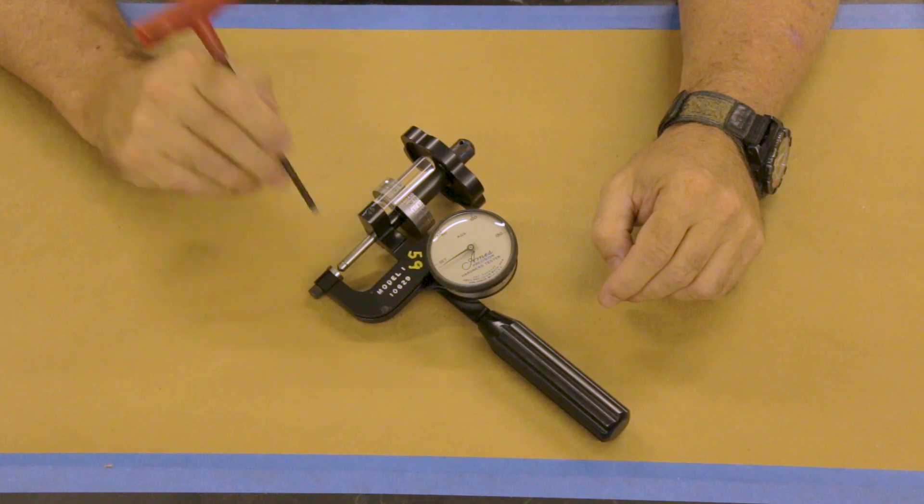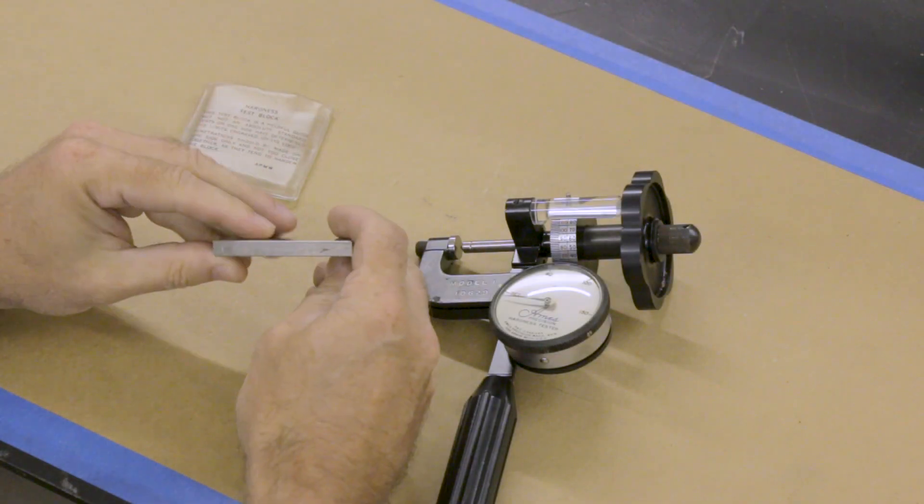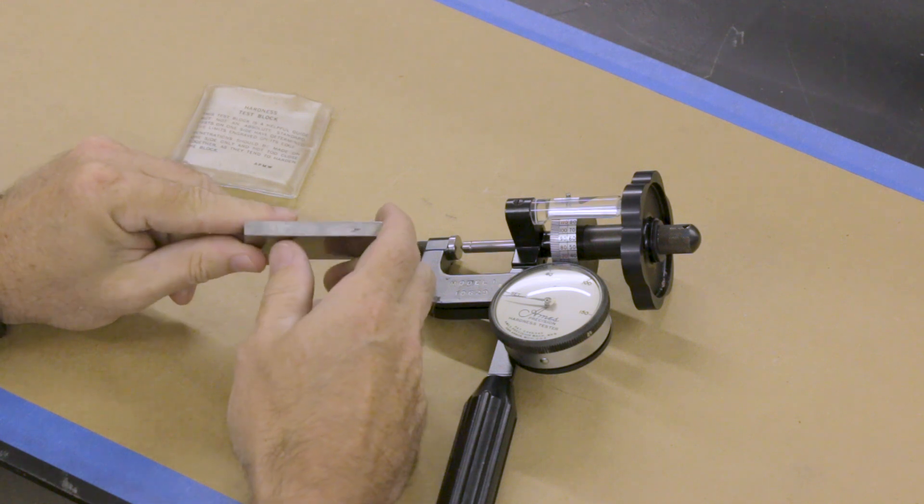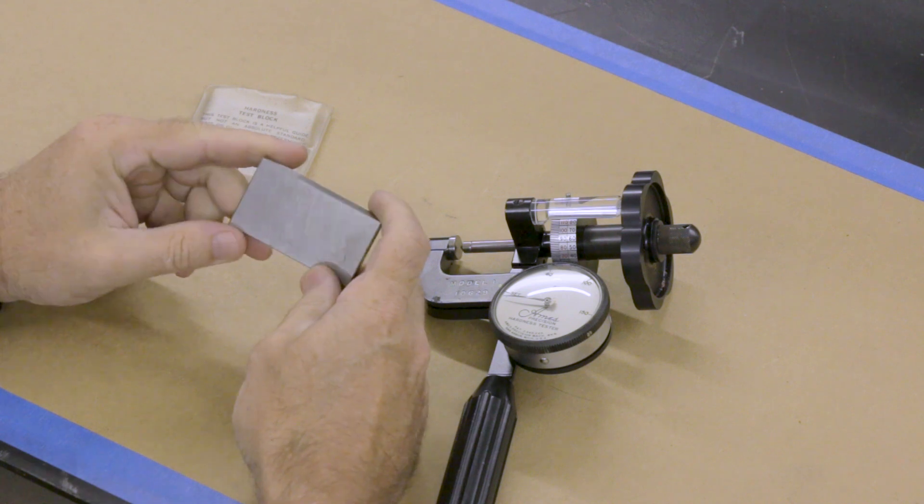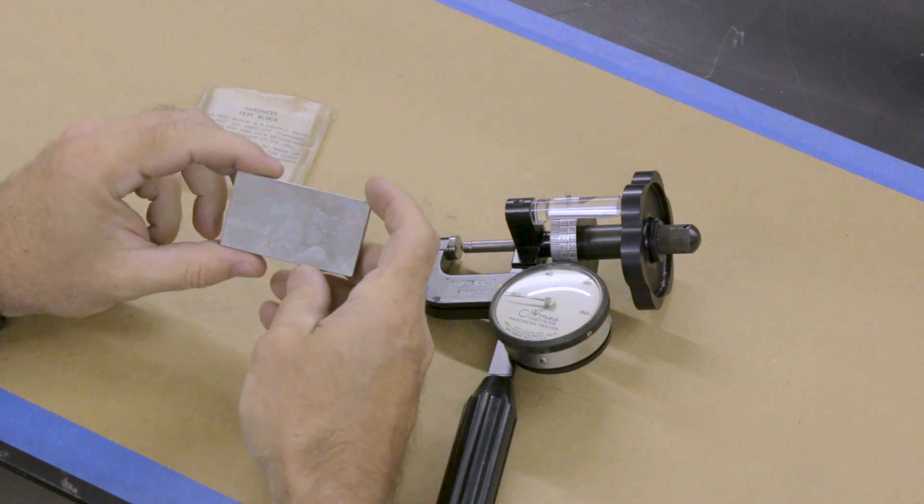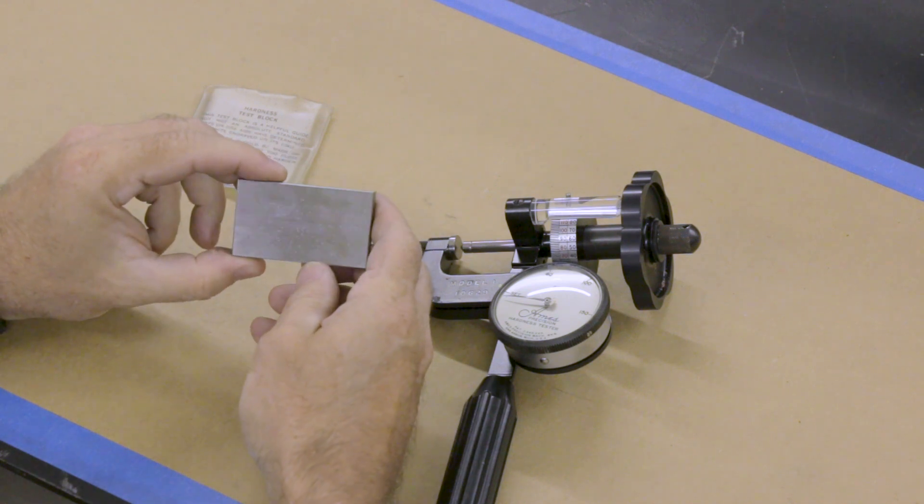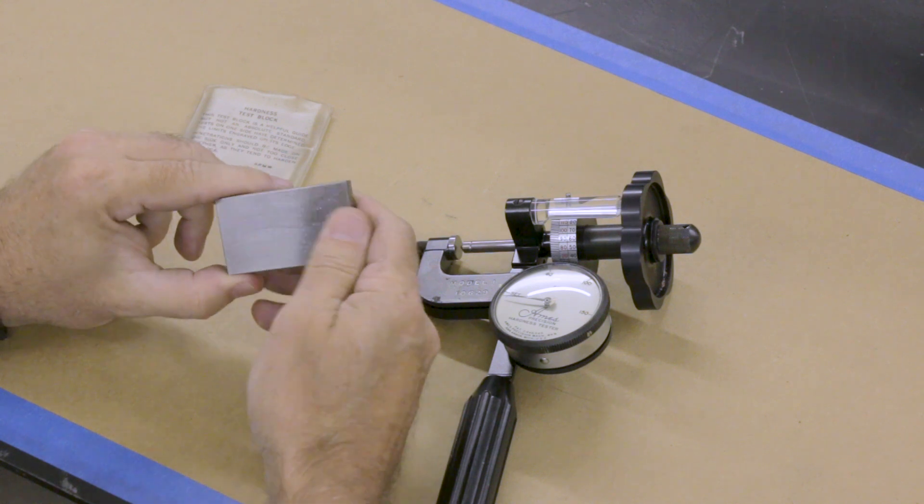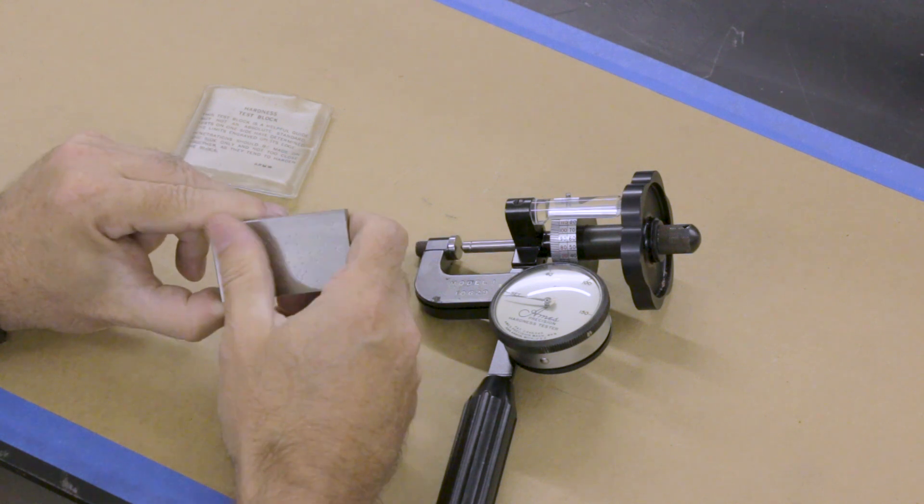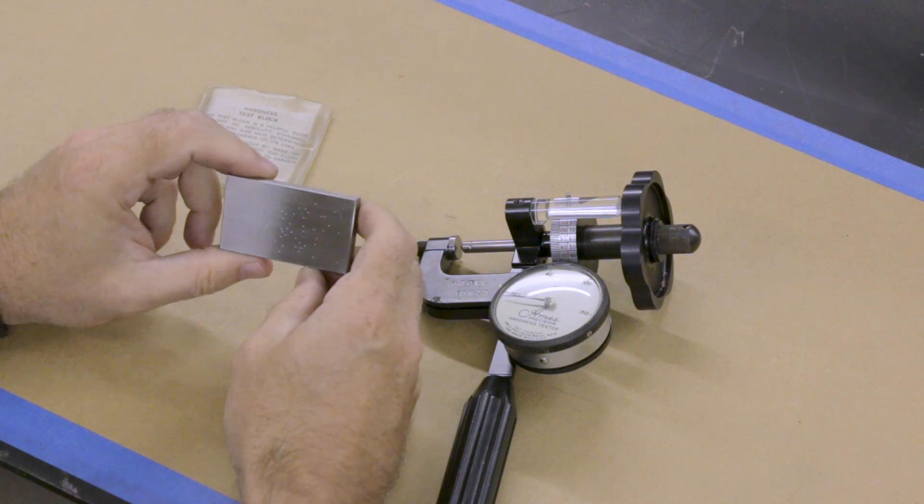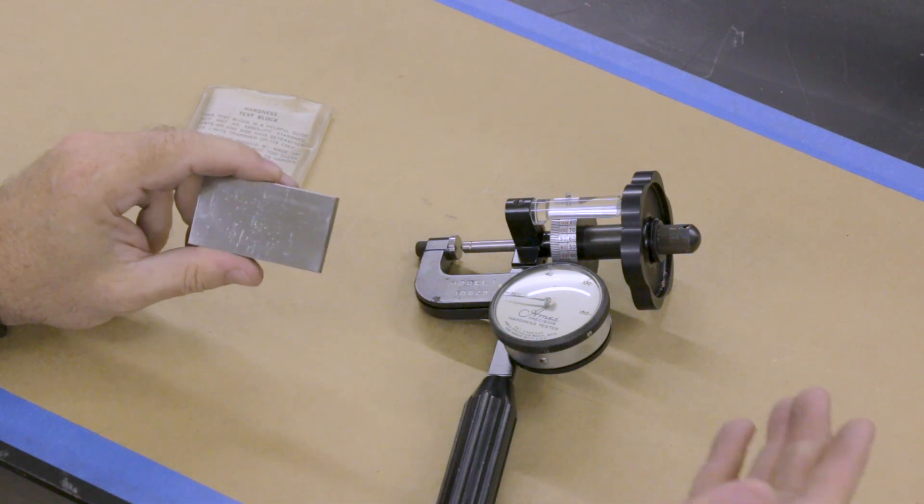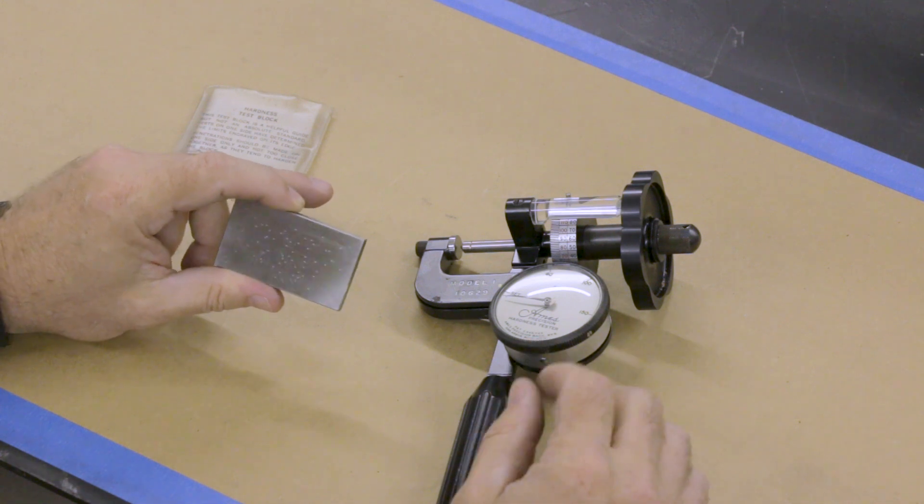Alright, so a hardness tester should come with some kind of a test block. And this one is marked on the side, I don't know if you can see it, but it says C64. So this block is verified hardened to Rockwell 64. Now when I got this hardness tester, it came with this block and another one that is, I believe, eight points lower. So I can test it against two different blocks at different hardness levels.